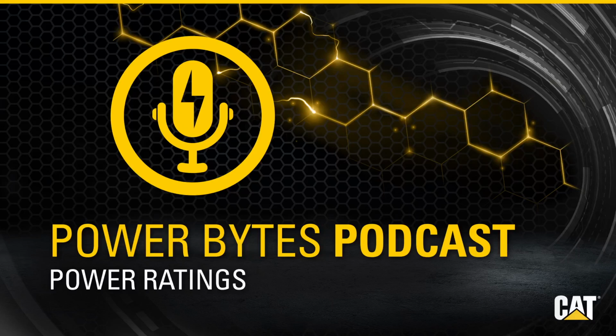Over time, if we were to assume that that's our standby generator set and that's the rating, if we were to take that same generator set and look at it in a prime application, so the same physical material rated for a prime application, we're now talking about a generator that can operate with unlimited hours. So for our 70% load factor, we would reduce the overall rating for the generator to 2,250 kVA, and that would put our 70% load factor at 1,575 kVA.